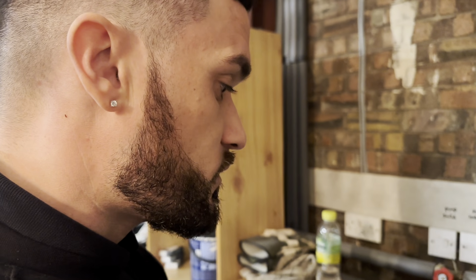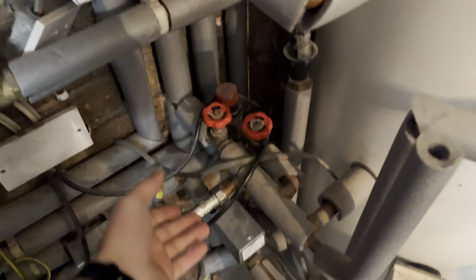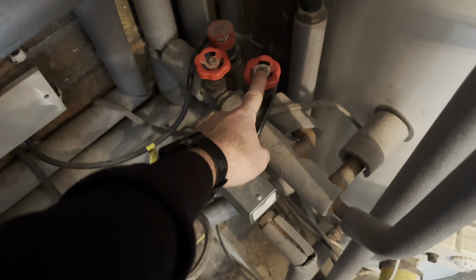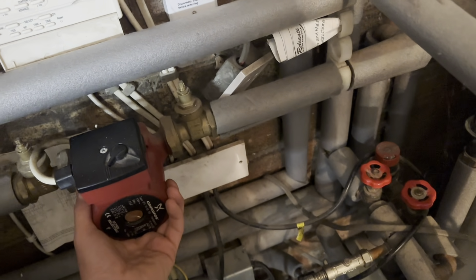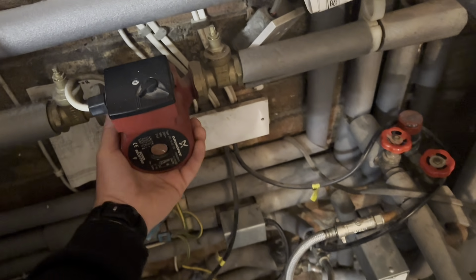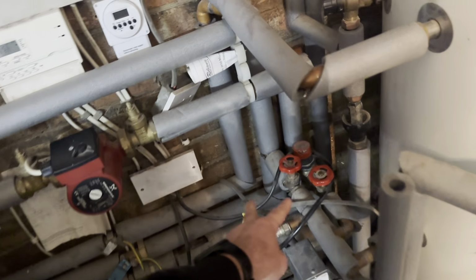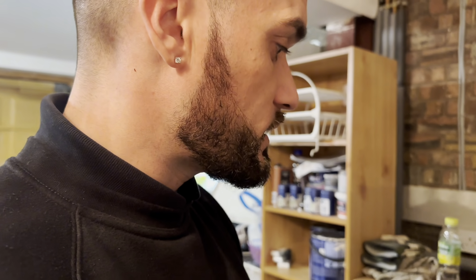We're going to force the system to a state where we'll ramp the hot water flow down, ramp the bypass valve down as well, so the pump's got to work, not necessarily harder, but when heating's in demand, it has to flow around. When we came last time, these were fully open, so a lot of these systems, S-plans especially, it's just understanding how they work, characteristics and everything else.